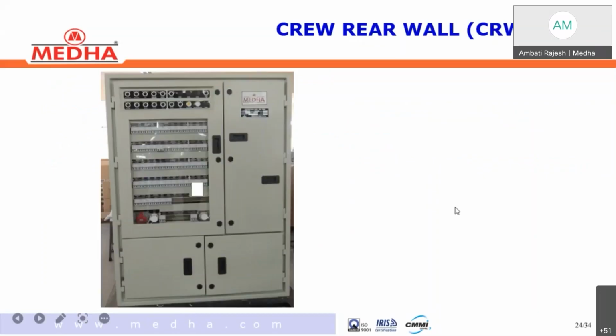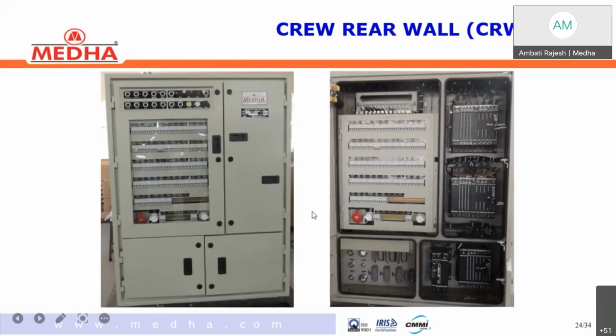Next, the CRW panel, crew rear wall panel or cab rear wall panel. This panel is from MEDHA and it is placed in each DMC coach just behind the driver seat. This is part of the HT compartment facing towards the driver cabin. Okay, a closed photograph, and in open view we can find it like this. So in closed condition only the switch panel and breakers panel we can see. We can access the switch panel and the remaining everything will be in locked condition. And if you open the doors, we can find internally like this all the MCU1, MCU2 computers, RIO computer, remote monitoring system computer, remaining all breakers, switches, Ethernet switches, contactors, everything placed inside this CRW panel. It is important for the entire TCMS to control at individual basic unit level as well as for train level controls. All the main important computers are placed inside this unit. Okay. And this is purely a MEDHA CRW panel.